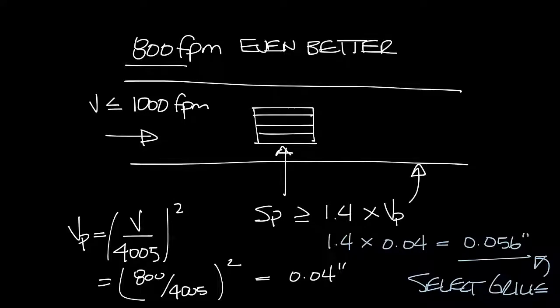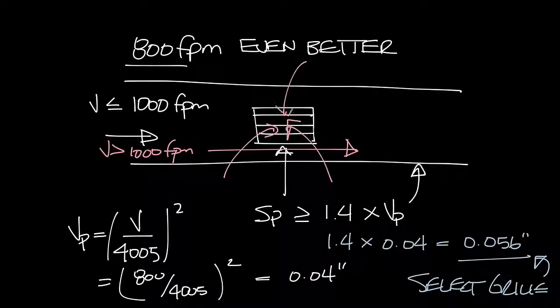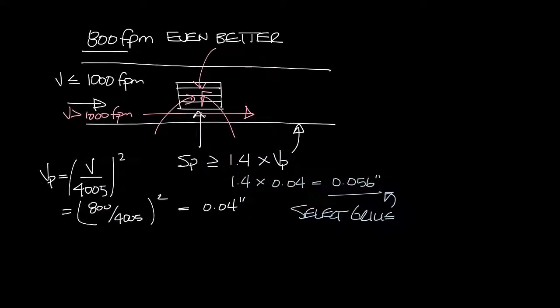There are a couple of things I want to add to this. If you have your duct size so that your velocity is higher than 1,000 feet per minute, the air is going to be moving by pretty quick and it's not going to go out. In fact, it's going to induce air into the grill instead of supply air into the space. The other thing is if there's not enough static pressure across the grill face, it's easier to pull the air in from the space as the air is moving by through the ductwork than it would be to blow the air out. So it's going to, again, induce air in.